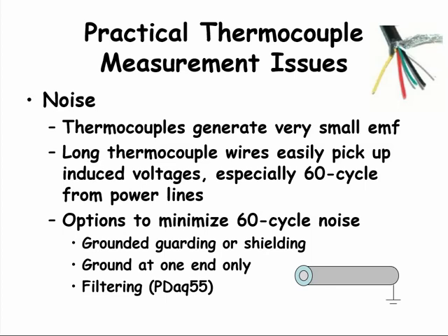The other method for managing noise, especially 60 cycle noise from power lines in the US and 50 cycle in Europe, is to use a filter. Filters can mitigate noise, especially 50 and 60 cycle noise. We will talk about filters near the end of the class.